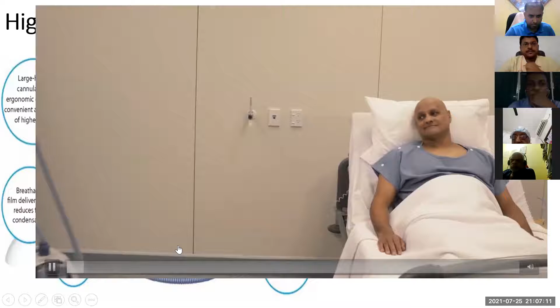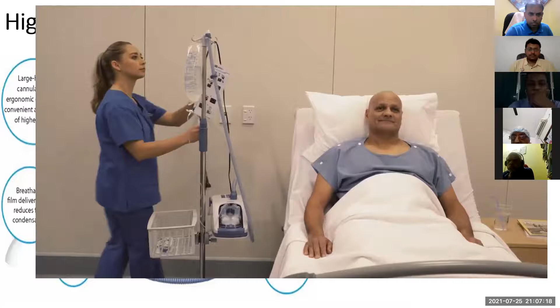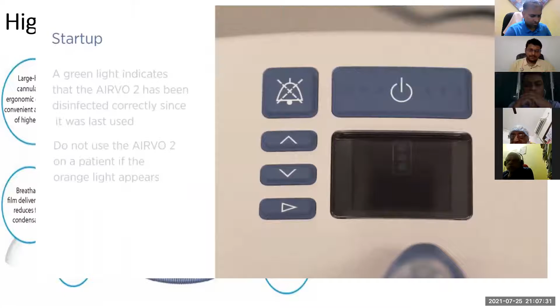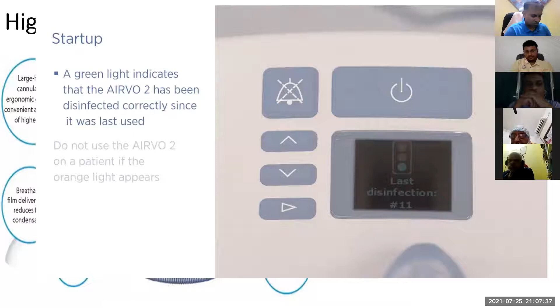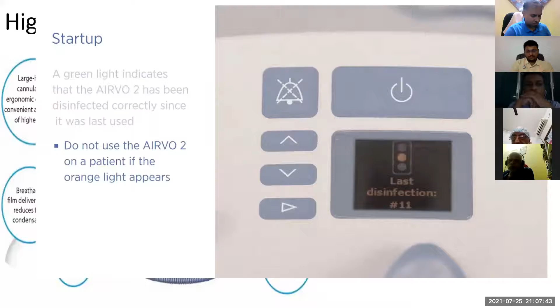With setup complete, the AIRVO 2 is now ready for your patient. The AIRVO 2's power cord should be well secured to the rear of the unit before plugging into the mains utility power socket. This is the machine we are using in most of the PICUs in India. Switch on the AIRVO 2 by pressing and holding the on-off button for 5 seconds. The unit will show you whether it is safe for use on a new patient. A green light indicates that the AIRVO 2 has been disinfected correctly since it was last used. However, do not use the AIRVO 2 on a patient if the orange light appears. You must dispose of the consumables and reprocess this AIRVO 2 before it can be used.